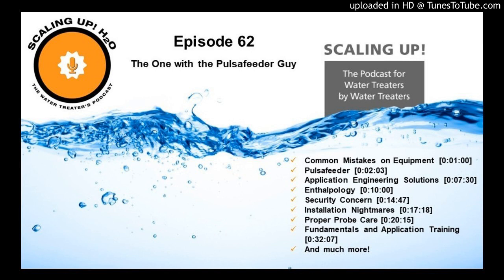It's taking a broad measurement and it's averaging it. Doing that makes the probe way more accurate and far more resistant to fouling. You talk about scale buildup on this probe, you talk about things like biofilm, things that could interfere with your measurement. Using a toroidal style probe, you're prorating the effects of that fouling film exponentially to where it's almost not affecting the actual raw measurement at all.